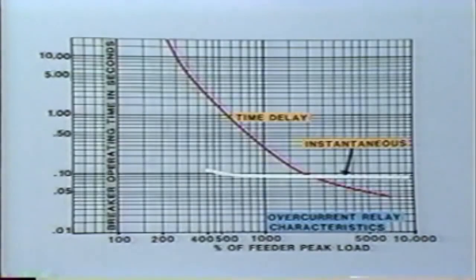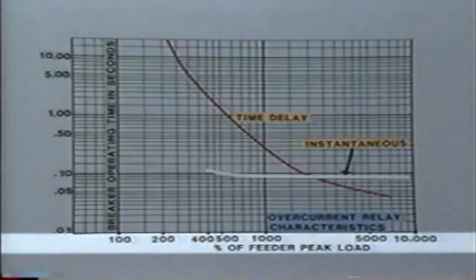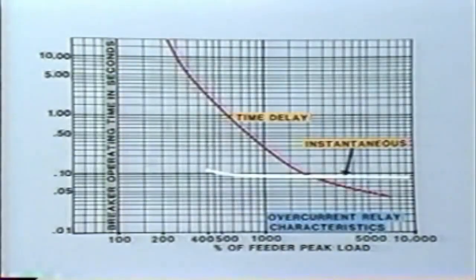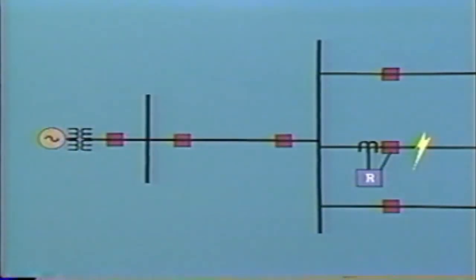The protective system must be able to measure and respond to its incoming signals in a very short time period. If the conditions are determined to be intolerable, then the protective system must take action immediately, usually to trip out circuit breakers. Conversely, if the fault is tolerable, then the protective system must not operate. In most power systems, the protective relays are rarely called upon to operate, but under fault conditions, it is absolutely imperative that they do operate precisely and provide the correct action. If a relay fails to operate and hence clear an intolerable fault, then equipment damage may occur, and certainly there would be a system upset.